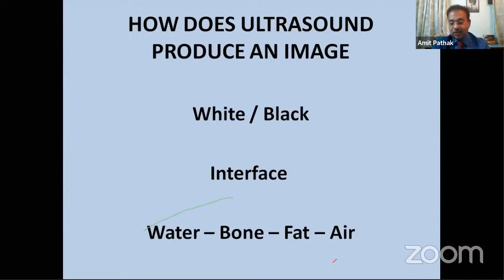So what is happening is this difference in density is causing complete 100% reflection of ultrasound, and that is the biggest deficiency of ultrasound. So the biggest disadvantage out of the other three which I discussed earlier is that whenever air comes, ultrasound goes to zero, and that is the problem which we have, which is actually only sorted out by a CT scan. So that creates our limitations beyond which ultrasound cannot evolve, because whenever air comes, ultrasound will stop, like obviously bone.